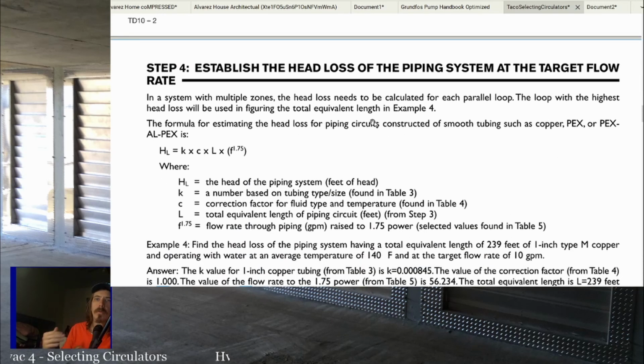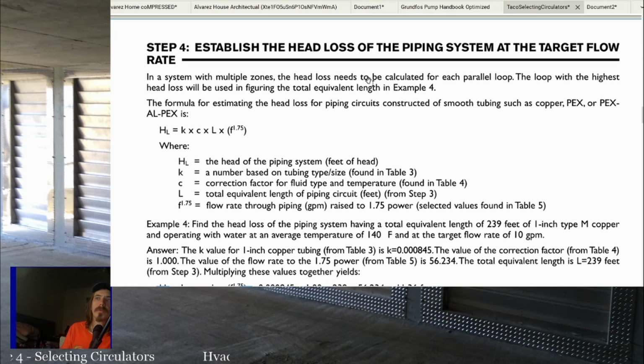Once you've got the equivalent length, we can determine the head loss of the piping at the target flow rate. In a system with multiple zone valves, the head loss needs to be calculated for each parallel loop. This is very important right here. The loop with the highest head loss is going to be the total length. Let's see if I can grab, will a highlighter work? Yeah. This is the same for any system pretty much.